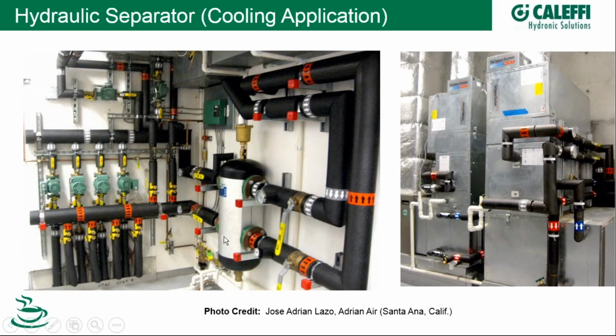On the left-hand side here, this is the chilled water side of his system. So he does a real good job. Coming off of the chiller, you can see marked in, call it gray arrows or maybe light blue, chilled water coming into the hydraulic separator, okay? The 4 or 6 zones over here are taking that chilled water up to the coils, absorbing heat, and then coming back here. So you've got cool water here from the chiller, returning back to the chiller. Chilled water going out to your zones, and then the heated water back here. So the same holds true for chilled water as for heating when it comes to decoupling.